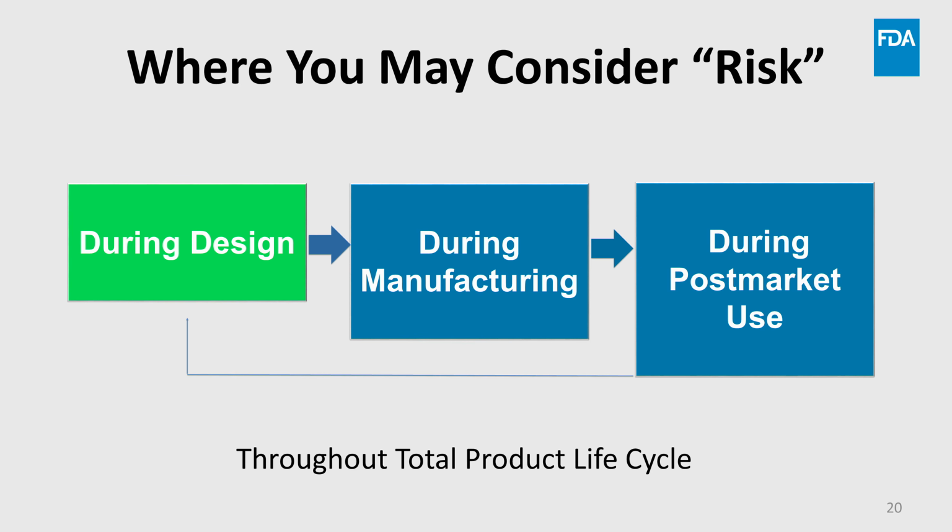From a practical standpoint, I can tell you the earlier you identify and understand a device's risk while designing the device, the better. It is understood in early design you will likely be making estimates and that it is very difficult to identify every potential risk. However, by the time you get to design validation, you need to have a good understanding of the risk of the device and confirm it.